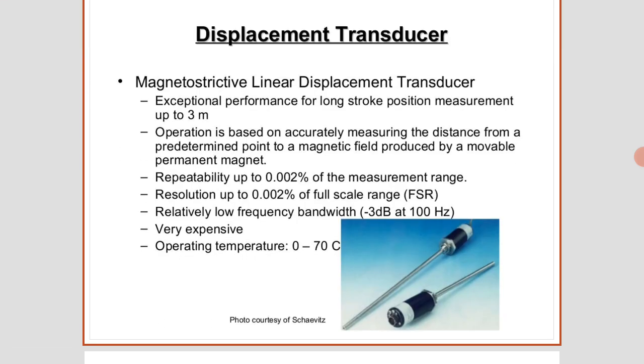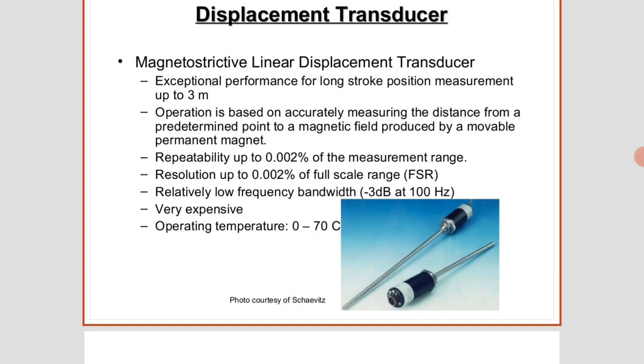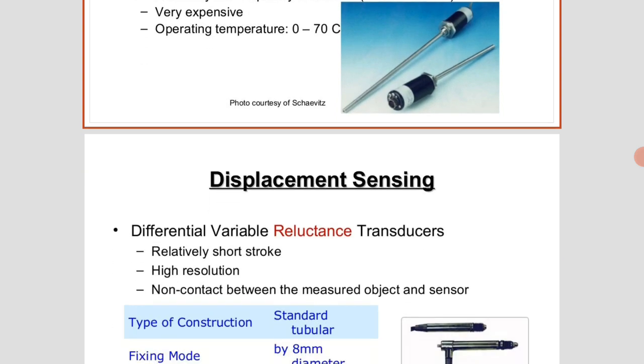displacement transducer, magnetostrictive linear displacement transducer: exceptional performance for long stroke position measurement up to 3 meters. Operation is based on accurately measuring the distance from a predetermined point to a magnetic field produced by a movable permanent magnet. Repeatability up to 0.002% of the measurement range, resolution up to 0.002% of full scale range, relatively low frequency bandwidth, minus 3 dB at 100 Hz, very expensive, operating temperature is 0 to 70 degrees Celsius.